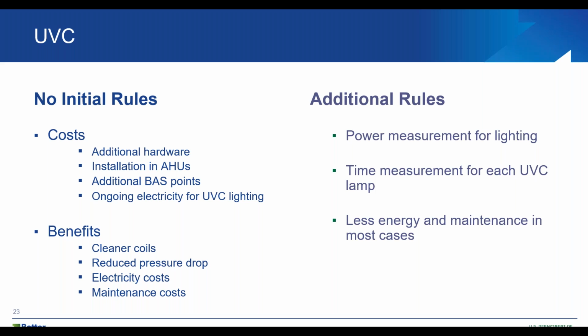And there are certain benefits as well, though, not just from the FDD, but you get cleaner coils typically if it's placed into the air handling system. So you could have less energy from lower pressure drops, as well as lower maintenance costs, as they don't need to go clean the coil as frequently because of the UVC. However, now we need to add additional rules for the additional equipment, such as adding power measurement for the lighting. We want to make sure that the lighting is on, and we also want to make sure that it's operating as expected. So one would be an indication of power to the lighting.